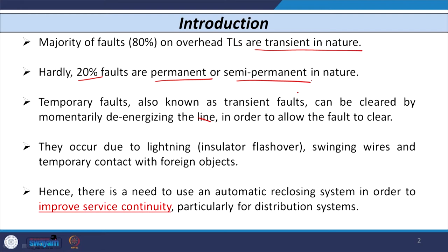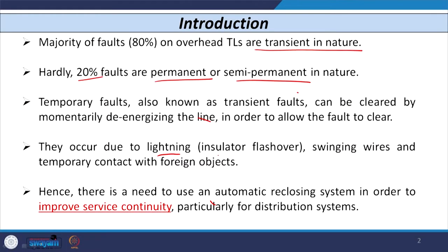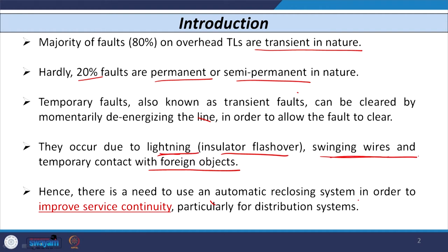Temporary or transient faults can be cleared by momentarily de-energizing the line. Whatever fault exists may not persist once we de-energize the line momentarily after the opening of the circuit breaker. These transient faults may occur due to lightning causing flashover of insulators, swinging of wires, or temporary contact with some foreign object.